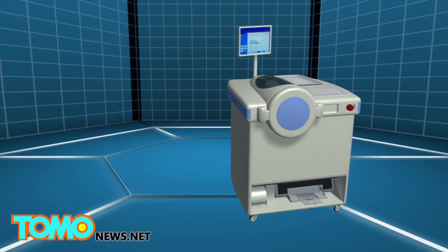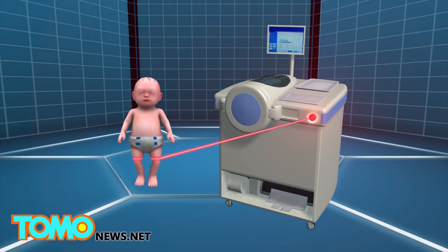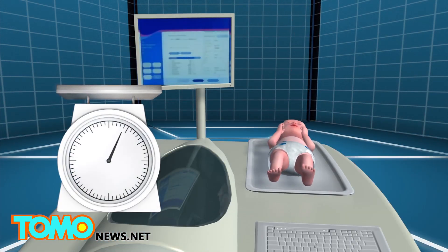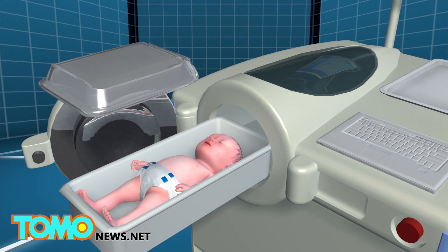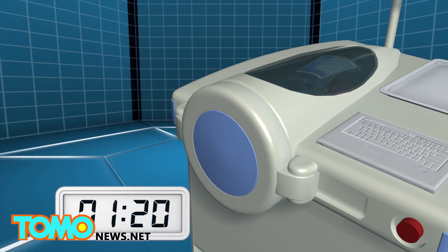The PEA POD is a medical device that uses air displacement technology to measure the body composition of premature infants. The baby is first weighed by the device's scale, then placed in an enclosed heated chamber for approximately two minutes, where its body volume is measured by the amount of air displaced by its body inside the chamber.